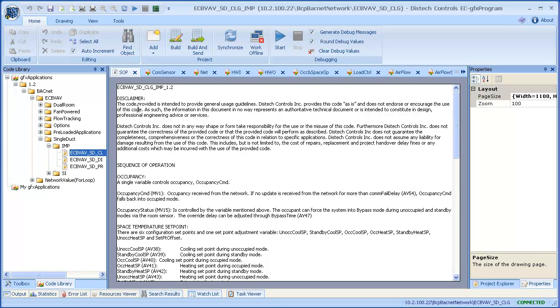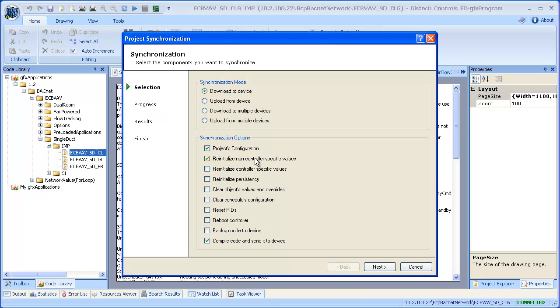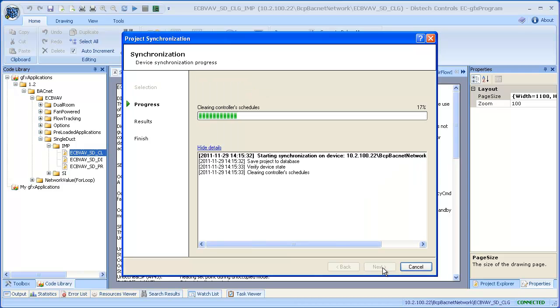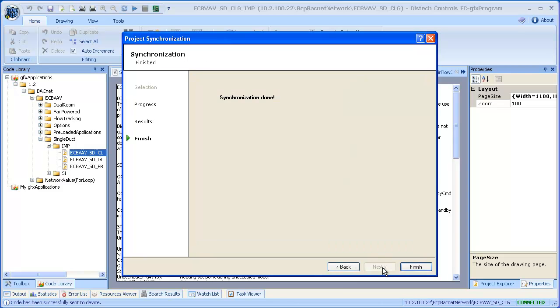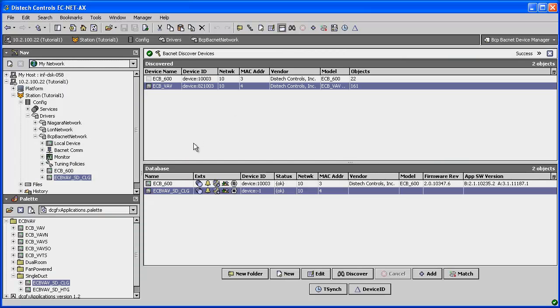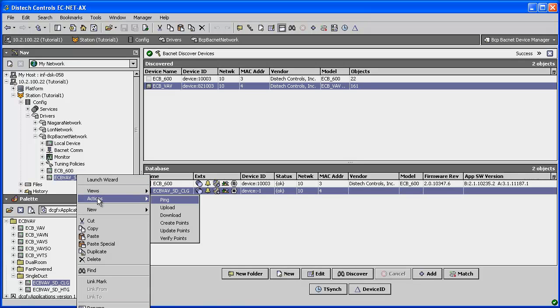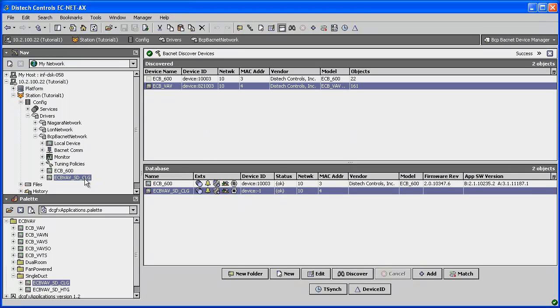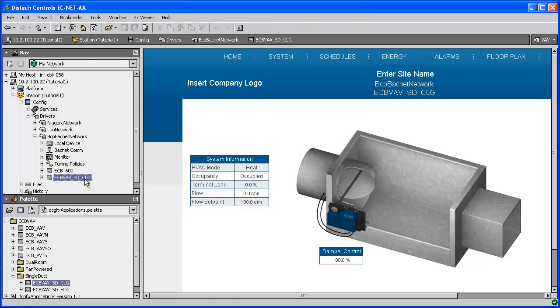The pre-engineered applications have been designed to be as flexible as possible while allowing you to easily modify the program according to your own needs. Once the application is open, we can simply build and send it to a controller. To do so, click Synchronize. In the Project Synchronization window, select the Basic Synchronization options and click Next to continue. The ECGFX program will build the program and send it to the controller. Once done, return to ECNet-AX and create the control points for the pre-engineered application in the controller by right-clicking on your controller, selecting Actions, then Create Points. Once the points are created, double-click on the controller to open the graphics page where you can view the device's live data.